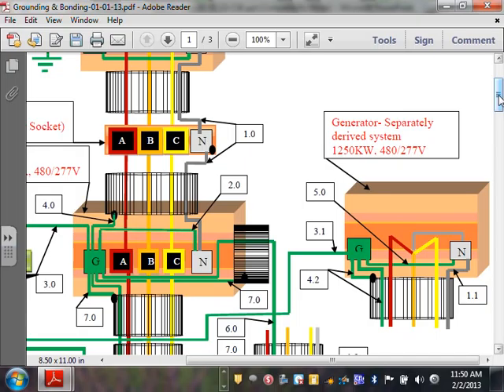If you're running a separately derived system and you have an auto transfer switch, in this case, most likely you would not have an auto transfer switch at this size. You tie directly to the switchgear, right? Paralleling switchgear. Then the only difference, you have to have 4-pole, right? So you have to add a 4-pole and break the neutral. If you broke the neutral, it's a separately derived system.